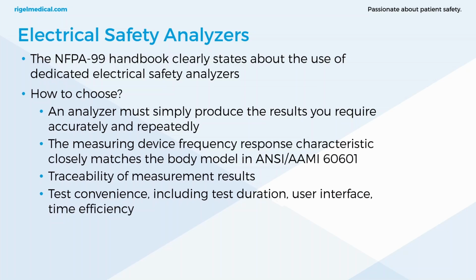What you may find is that an analyzer is specified in a manual. Rigel has their own safety analyzers recommended in specific service manuals, but realistically you don't have to use that safety analyzer. You can use any safety analyzer you want. It's just what's recommended. It's all about using an equivalent tester if you prefer that unit. So user preference is the overriding factor, as long as it's from a reputable manufacturer.